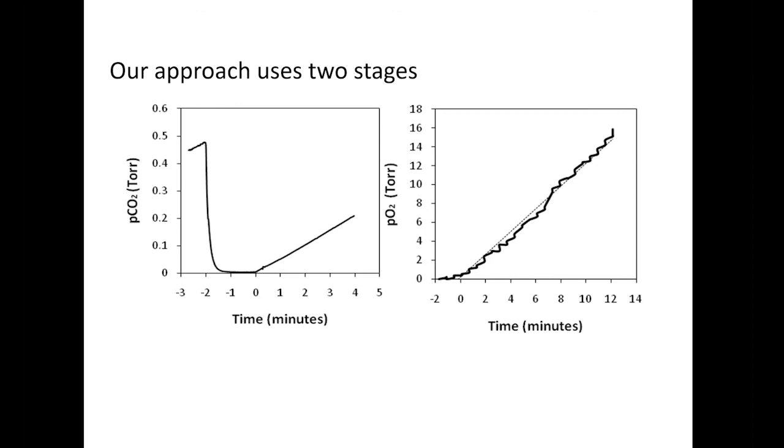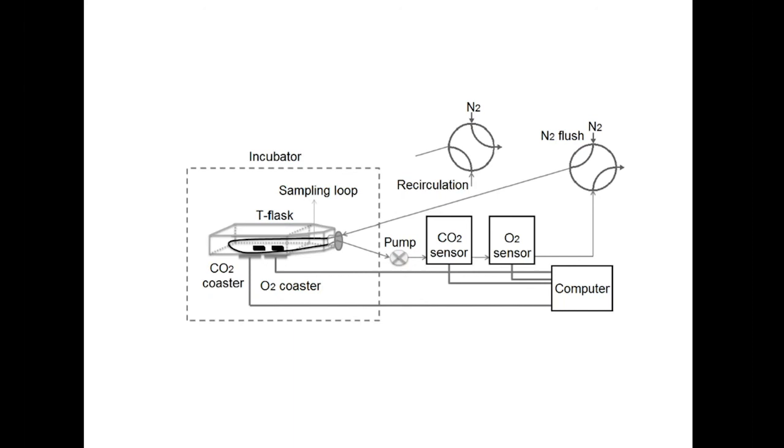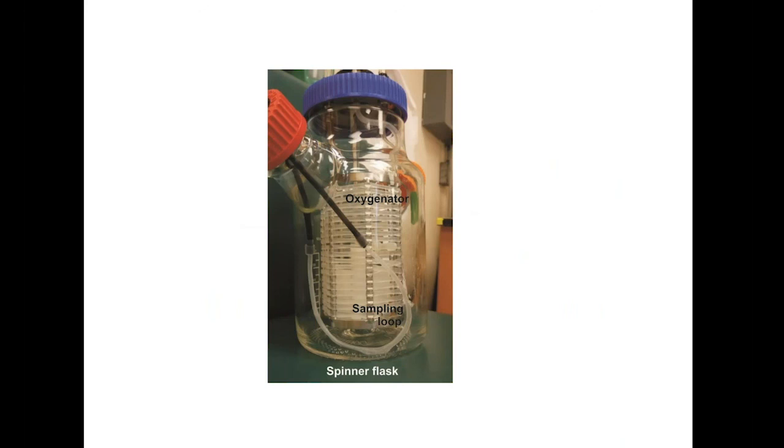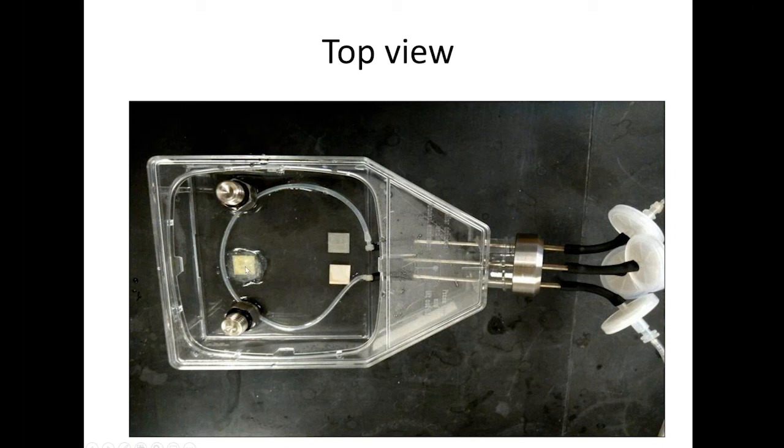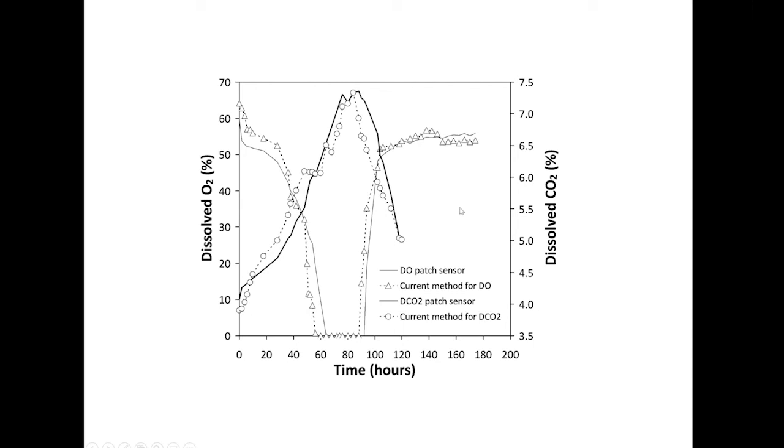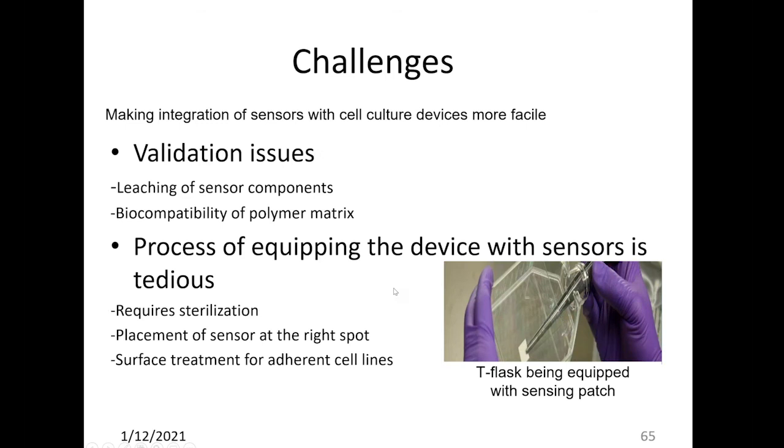We were able to build versions of this loop that could go into a T-flask or a spinner flask and effectively non-invasively sample space in a sterile fashion. And the sensors, everything comes out of the bioreactor. So from an FDA point of view, it's about as benign as you get. This is our prototype T-flask sensor. We put in our silicone loop and also put a CO2 patch, pH patch, oxygen patch, and did all the validation studies to show that this is actually measuring as it's supposed to measure. So we now have non-invasive measurements.